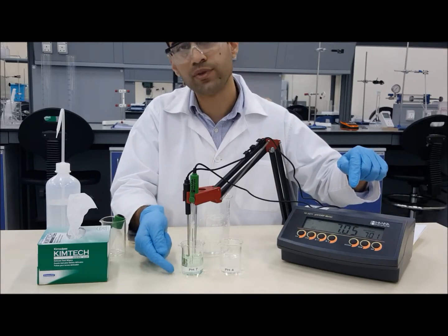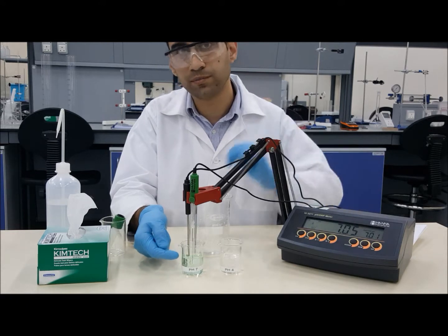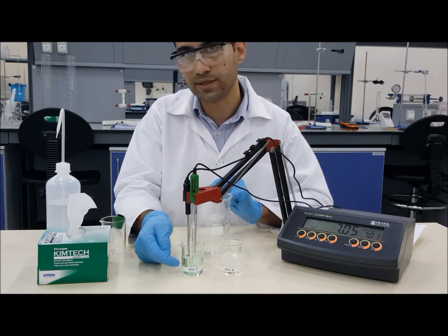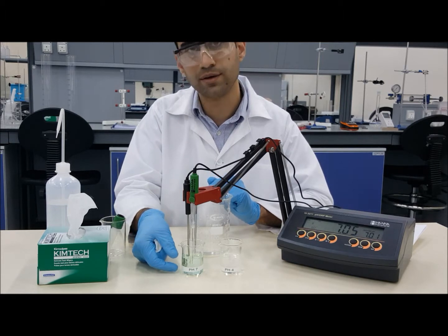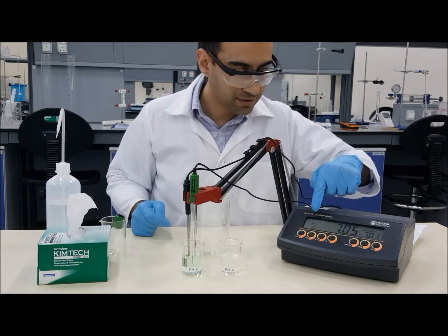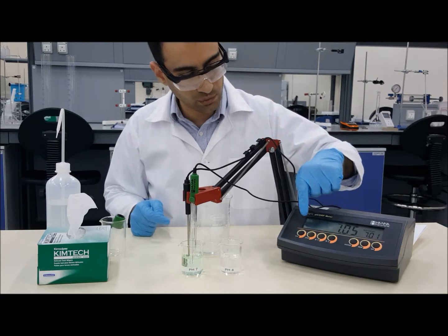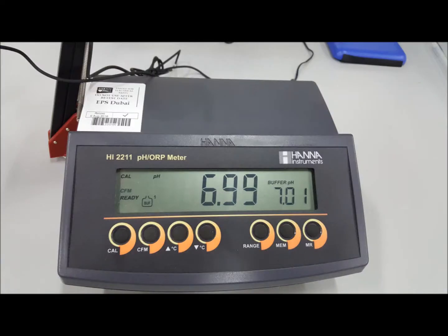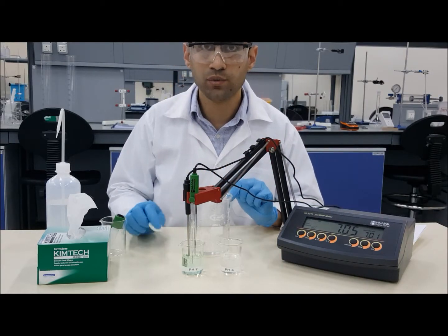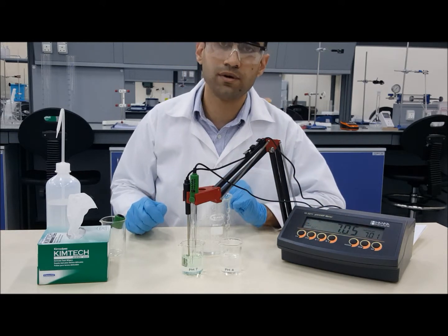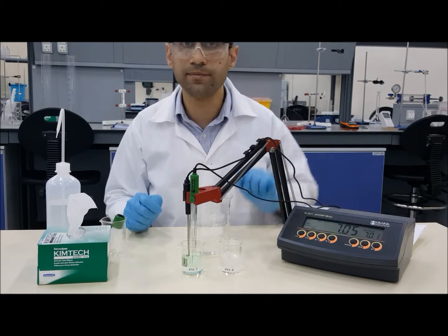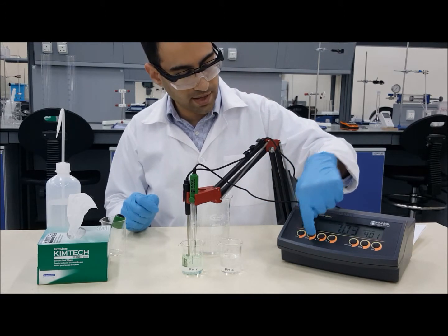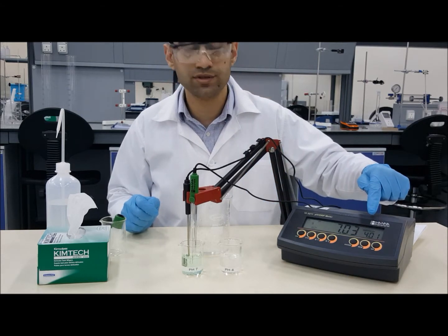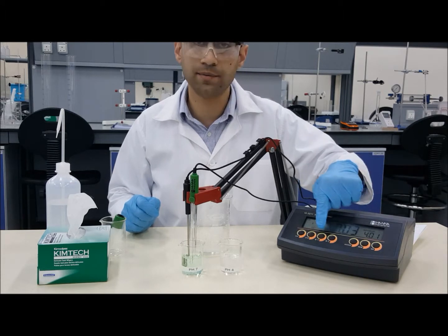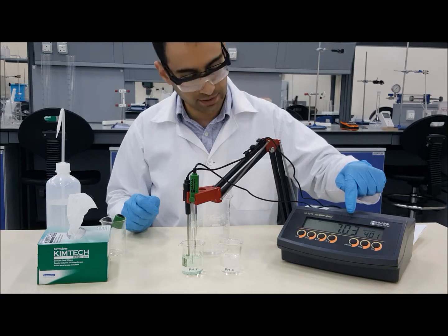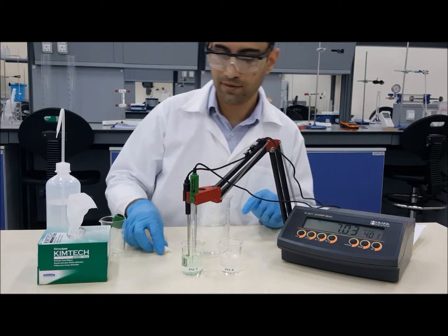We need to make sure that there is about 3 centimeters of buffer solution for the calibration purpose, so the electrode should be submerged at least 3 centimeters. Similarly, while taking measurements, 3 centimeters of any chemicals will need to be above the electrode. The flashing screen is still there, and we will need to wait till we get the ready message in there. As we get the ready message, we will need to press on CFM, which is confirming the readings. So the second button, CFM, needs to be pressed now. And as we press that, the buffer requirement is changing now. We can get 4 here. Again, we can use the up and down buttons to change that. Here we get the actual reading, and here again buffer is flashing.